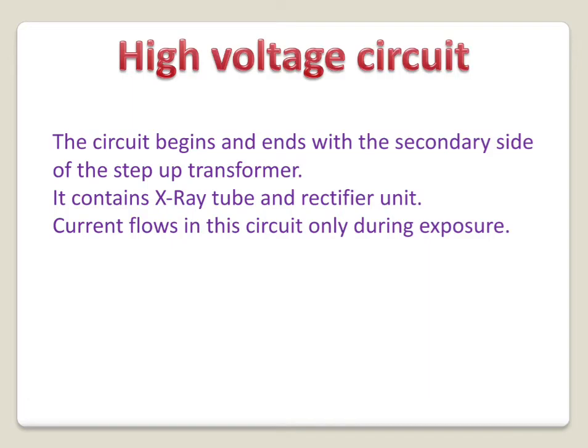In the high voltage circuit, the current flows only during the exposure time. The high voltage circuit is considered a dangerous circuit because of the high voltage, and because of that the cables supplied to the x-ray tube have to be highly insulated, as high voltage is being carried by these cables.